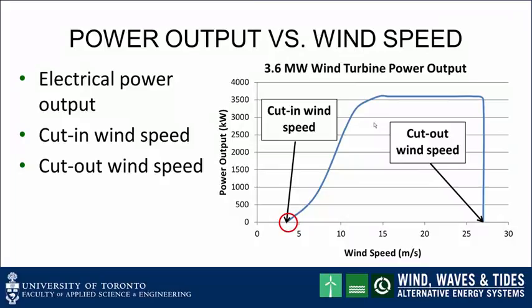Similarly, for this wind turbine, the power output is zero at a wind speed of 27 meters per second. This upper limit is called the cut-out wind speed and is designed to protect the wind turbine from damage. No power is produced for wind speeds higher than the cut-out wind speed. Strategies employed include braking and locking the rotor in place to prevent it from turning, protecting against damage in very high winds.